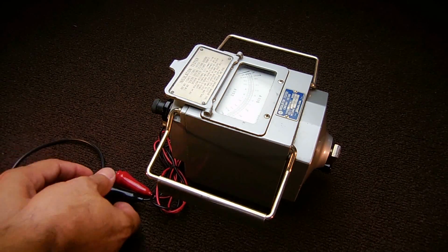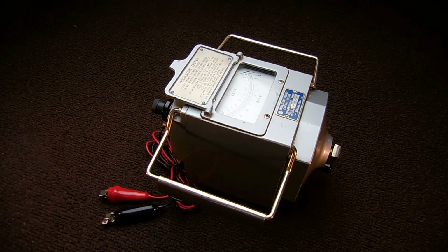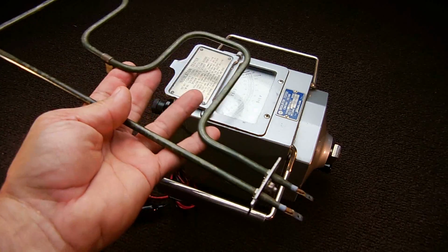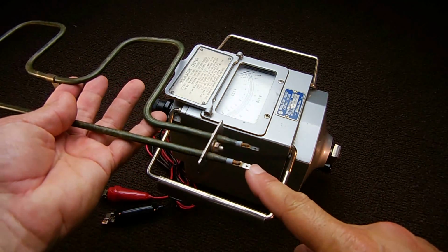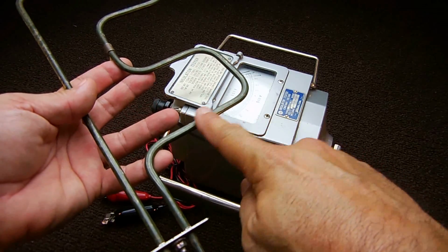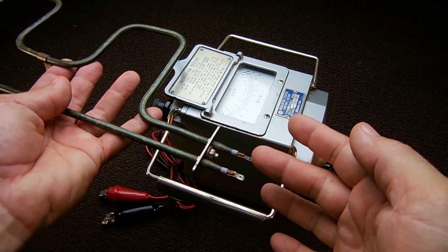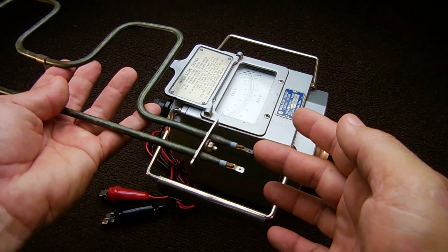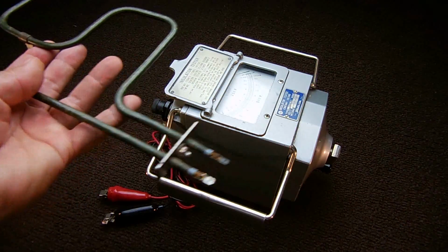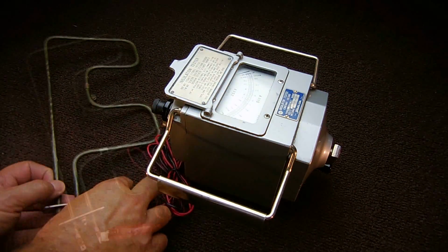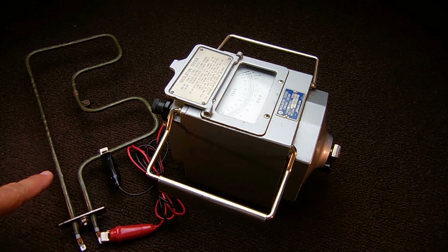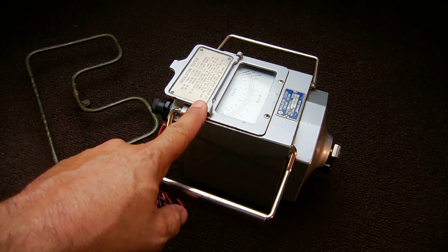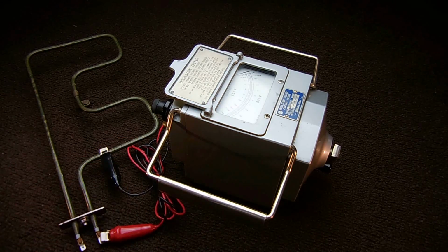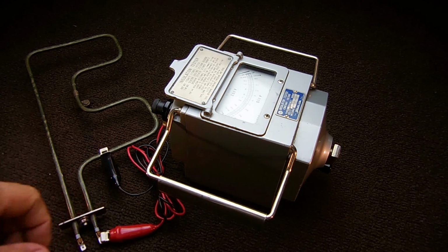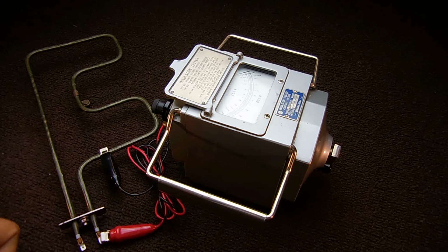Same thing. Now we're going to take a look at a heating element. Like you see right over here, we're going to take one wire connected to one of the terminals, the other clamped on the outside, and we're going to see how well it's isolated between the tip and the outer jacket. Since this is a 120 volt heating element, I'm going to leave this on a 250 volt setting. We're going to crank it. You want to make sure that the resistance reading is well above 2 megohms. Here we go.